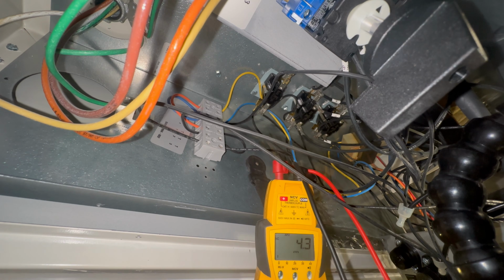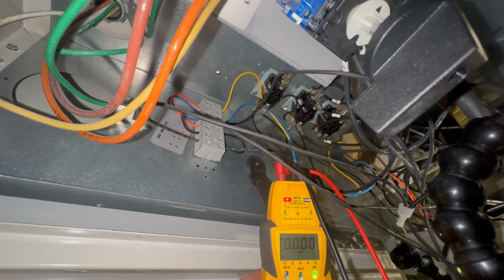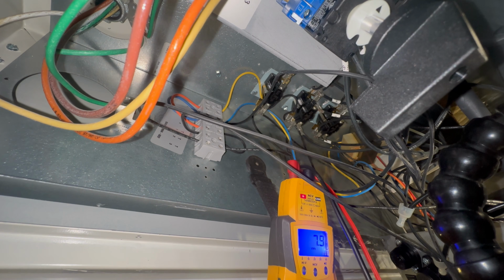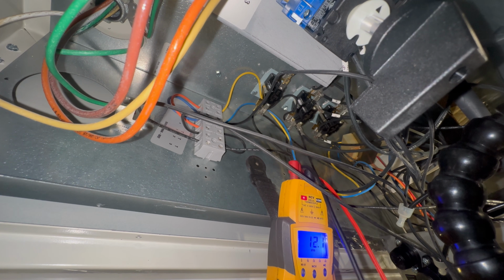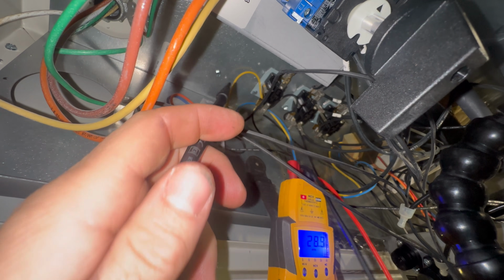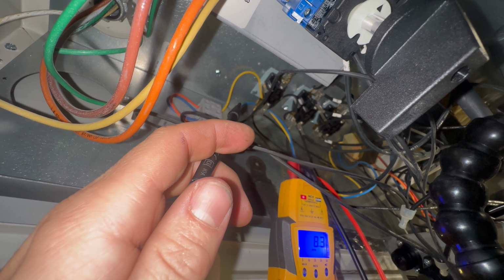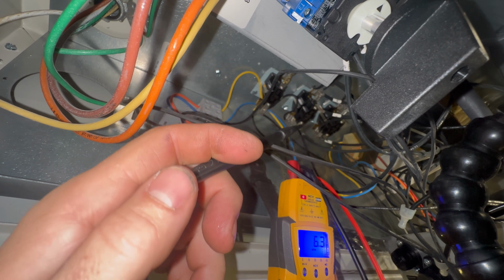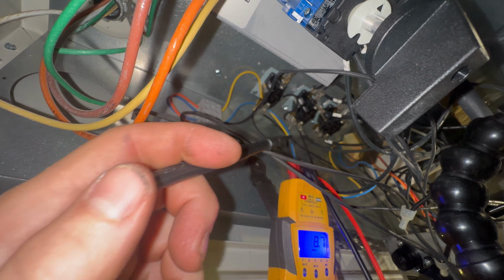I want to make sure that we have control voltage, or 24 volt, first off, because that is our control voltage that opens and closes the contacts and the relays that sends power to the heat and the fan. And we've got yellow and blue coming from our transformer way over there.